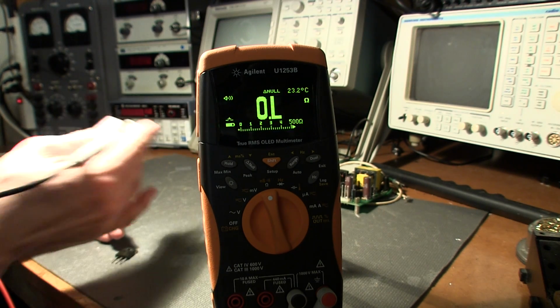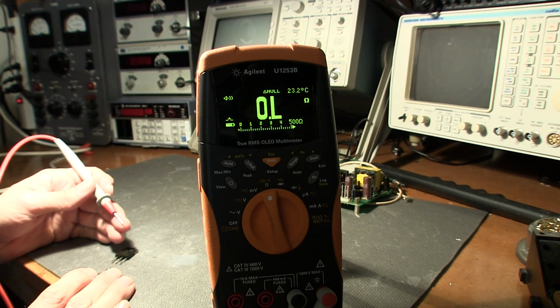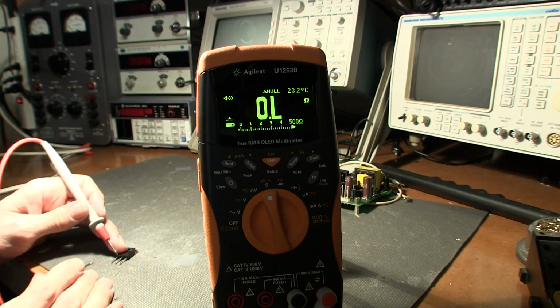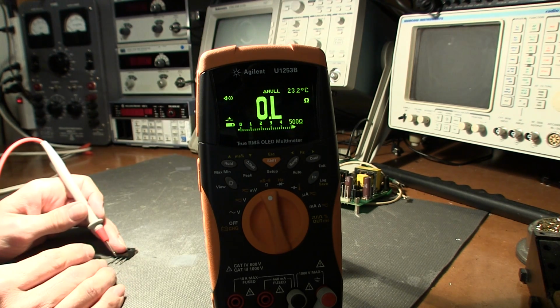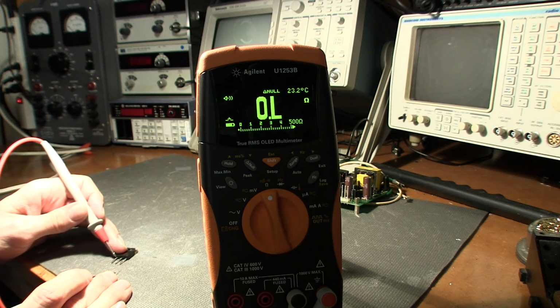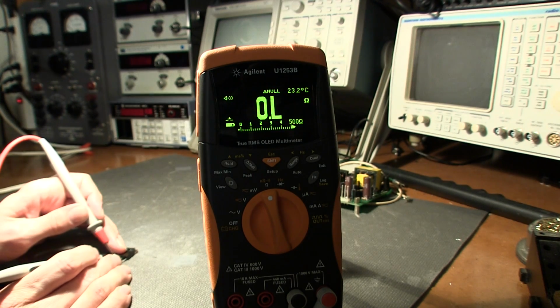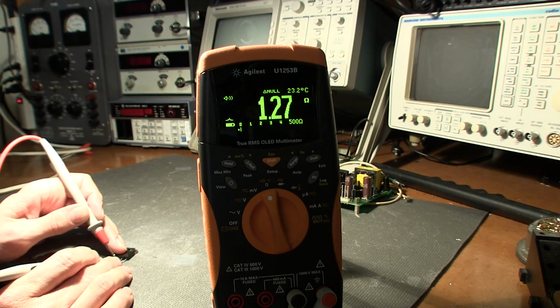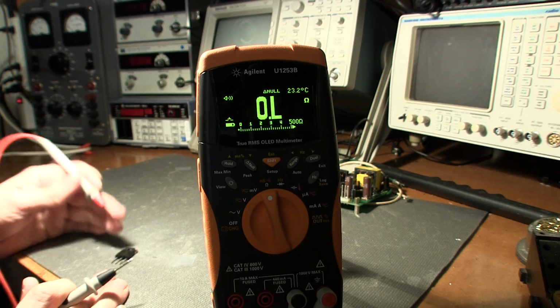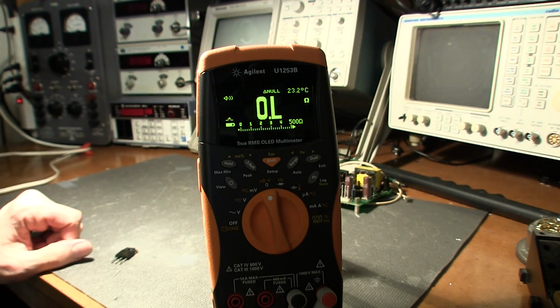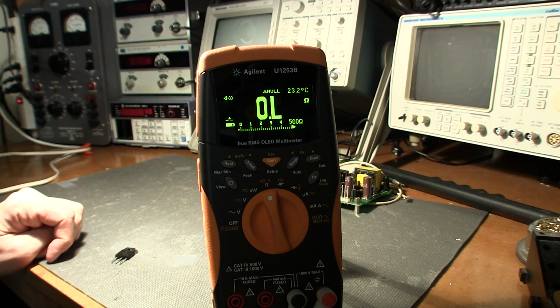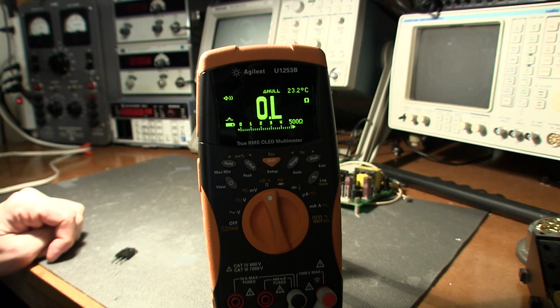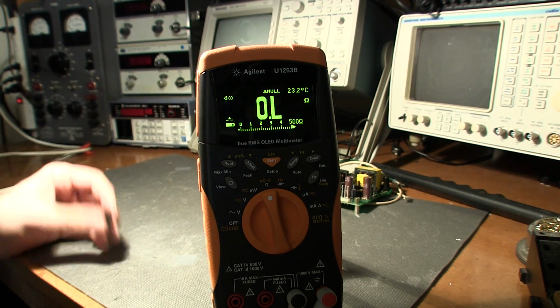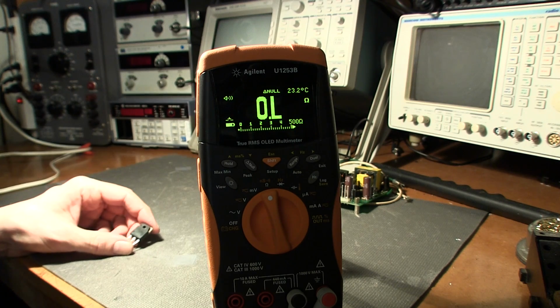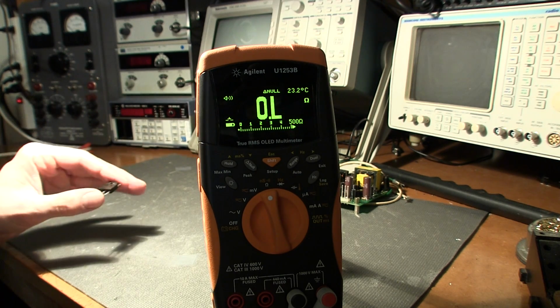The reason the main oscillator IC went is because there's a direct connection from that IC straight to the gate through a 5.1 ohm resistor. So if we look at the gate to the drain and the gate to the source, it's a dead short. That tells us we had a high voltage path directly into that IC. I'm surprised a chunk of that IC didn't blow out of it—it was actually still intact. So, pretty bad failure mode here.